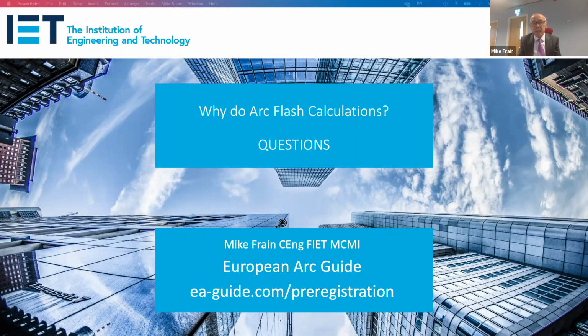The other thing we mention in the fact file is that there are instances where you ought to be wearing certain PPE. If you're working in control equipment where there's an arc flash hazard at that point, even if it's 0.3 of a calorie at the head and torso, the nearer you get to the arcing source, the higher the incident energy level is going to be.